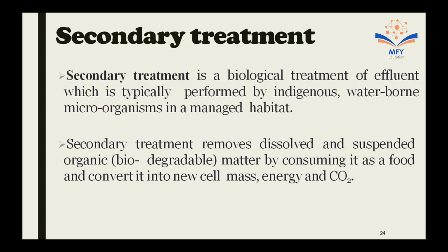Now, secondary treatment is a biological treatment of effluent which is typically performed by indigenous waterborne microorganisms in a managed habitat. Secondary treatment removes dissolved and suspended organic biodegradable matter by consuming it as food and converting it into new cell mass, energy and carbon dioxide. The most common microorganisms are bacteria, aerobic or anaerobic, maybe protozoa and rotifers. The least common are fungi and algae. After secondary treatment, almost 70 to 90% of BOD and 80 to 90% of dissolved solids are removed from effluent.